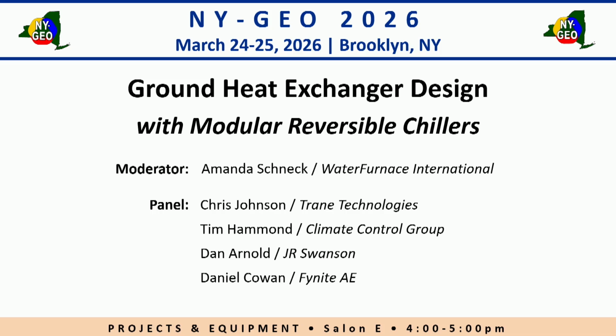On that, we have several data floors in our building right now, and we're using the heat generated by the data rooms to provide reheat and comfort to the space level. So we all know that there's a prohibition against simultaneous heating and cooling, but there's an exemption if it's site recovered energy. And so we're allowed to use that and provide a higher level of comfort. Now, when we talk about efficiency in simultaneous heating and cooling, you have to look at the compressor lift, right? So if you want to run just enough machines in your simultaneous mode to meet that recovery spot, and then you want to use something on the net water to hot water to make that additional heat that you need.